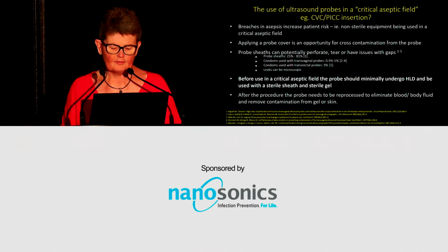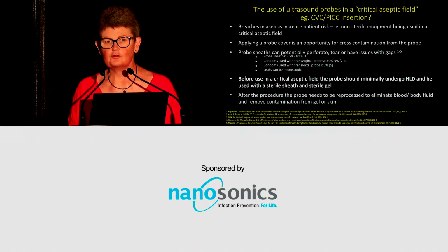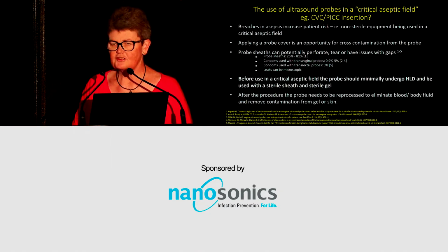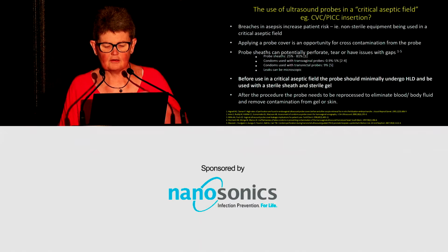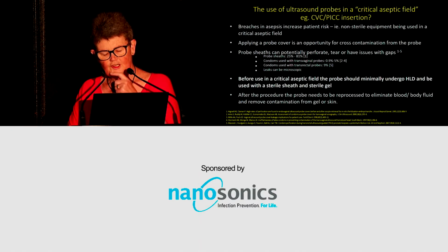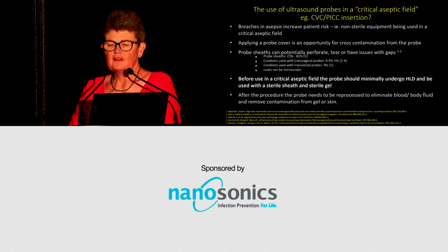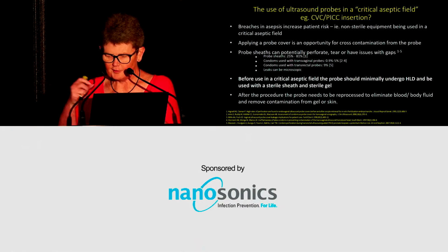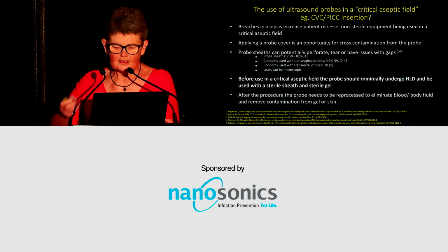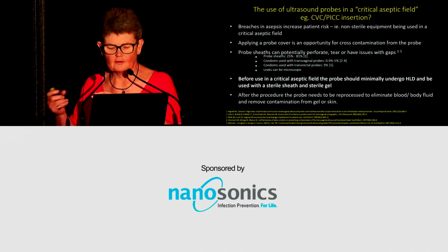I've spoken enough, I think, about the potential perforations, tears, or even issues with gaps around the top of these sheaths, and you can see there in different procedures that there are a range of percentages as to how often those breaches or tears may occur. What we know is that before they're used in a critical aseptic field, the probe should, at a minimum, undergo high-level disinfection and then be used with a sterile sheath and only a sterile gel. After the procedure, you're dealing with not only procedural contamination, but also the need to reprocess that probe so that it's used safely on the next patient.